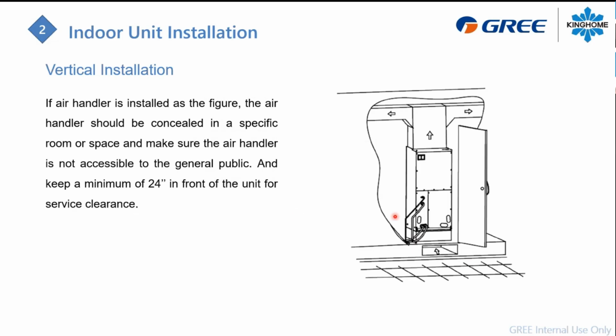So if your installation is vertical like this, you just make sure you have enough space around the unit to provide a good service on that unit. So you will need to have access to the top panel right here. You need 24 inches minimum in front of the unit, but side by side it can be as close as 1 inch, and in the back too. But in front of the unit, to get a good access to the top panel here is a good thing to know when you're installing those here and there.